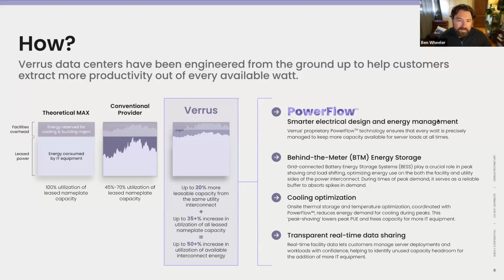So this is the total amount of nameplate capacity that customers - meaning hyperscalers, Google, Facebook, Meta, whoever - roll IT equipment into. Now within that leased capacity, generally only about 45 to 70% of it is utilized because there's a lot of variability, a difference between applications for cloud versus AI training versus inference. But as an industry average, about 45 to 70% of that leased capacity is used. So there's some headroom that's kind of gone to waste there, and there's headroom that's gone to waste in the amount of provisioning for cooling load on the IT equipment.